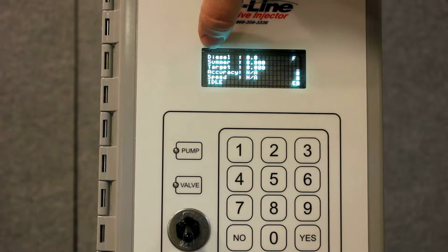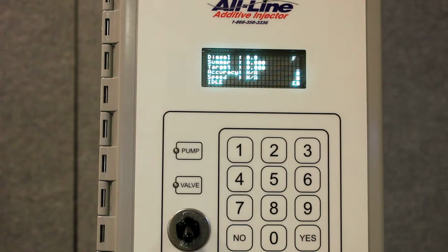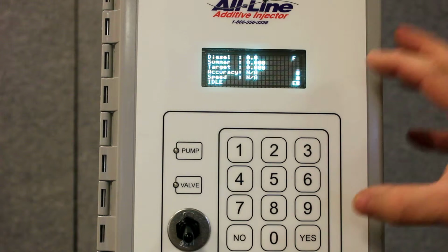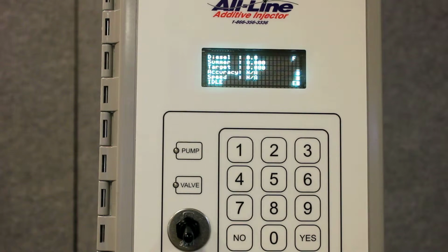On the top left is the diesel count. You may be using gas, but generally it's diesel. And next to that is the number of gallons. So as you pump diesel fuel to your customer and your LCR2 or Midcom or whatever you're using clicks off the gallons, this diesel count should match exactly the LCR2. That lets me know that the controller is accurately seeing the fuel you're pumping, which is very important for us to accurately put in the additive. We have to know what you're pumping.